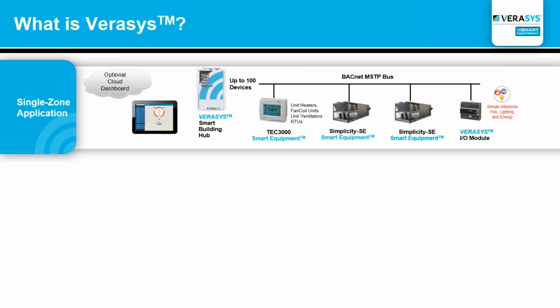The TEC 3000 on the third-party system is basically a controller, a BACnet controller, but it's a simple interface from a thermostat control into a third-party controller, a third-party piece of equipment. And the last thing you see all the way to the right is what we call our IOM module for Verasys. This is where I bring in other types of systems into Verasys itself - this could be lighting, a simple fire alarm input, or a meter, and that's how we bring other types of ancillaries into a Verasys system.